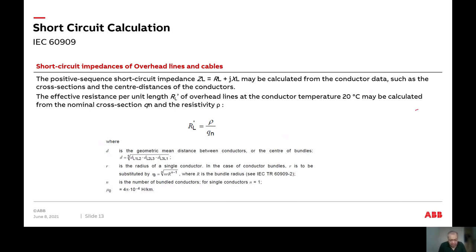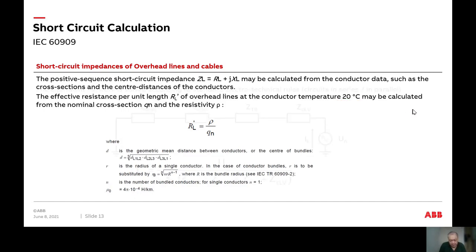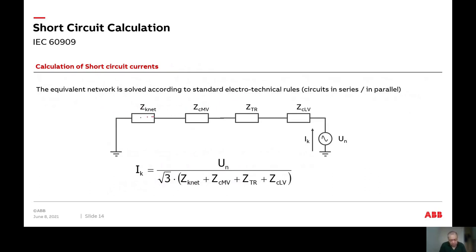For overhead lines and cables, the impedance data can be extracted from the cable data sheet. The conductor is normally rated at 20 degrees. The good thing about copper conductors is that when temperature goes up, impedance increases, which theoretically gives an additional reduction in short circuit current. As long as we use 20 degrees we are on the safe side, because as long as current is flowing the temperature will be quite high.